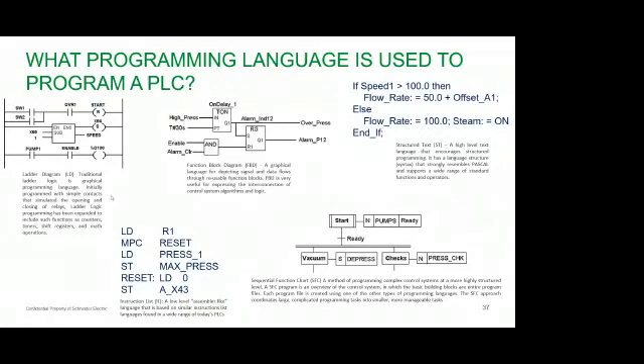This is called the positive rail. This is the negative rail. S1, SW1 is the switch or a push button which you use in the field. The IO will be connected to this unit, and when the operator pushes the push button, this gets energized. So power supply will flow from here to here, and this will be some other field device. When this field device's signal comes, it will help to start your motor. So R is your motor, for example. So when you turn on the switch, the power supply flows to here. When the field device gives permission, it will enable the motor to run. This is the basic concept you use to write a PLC program.